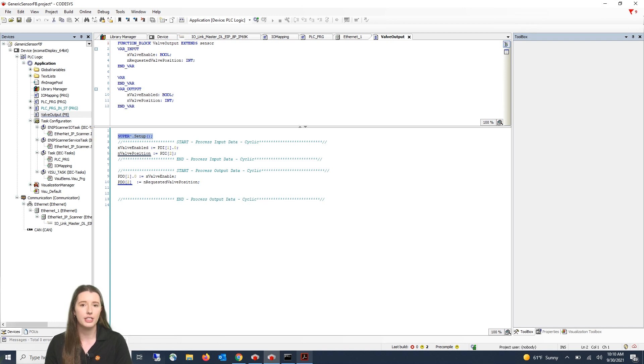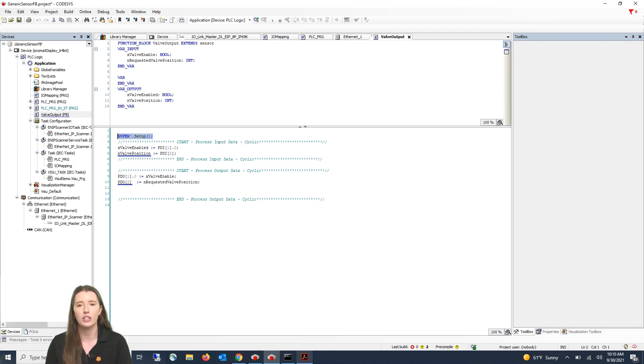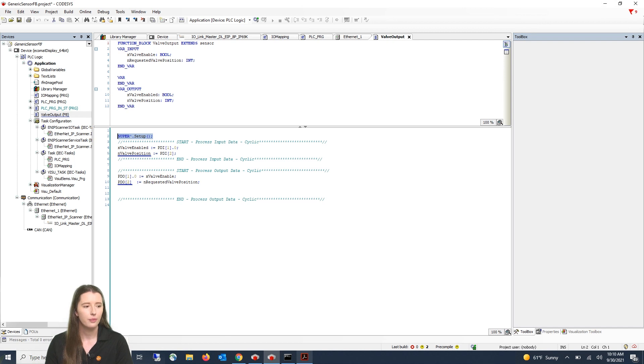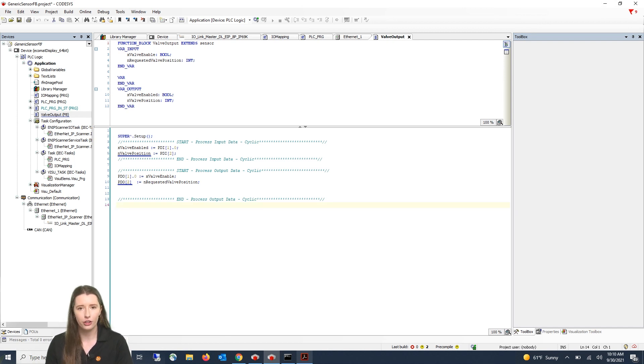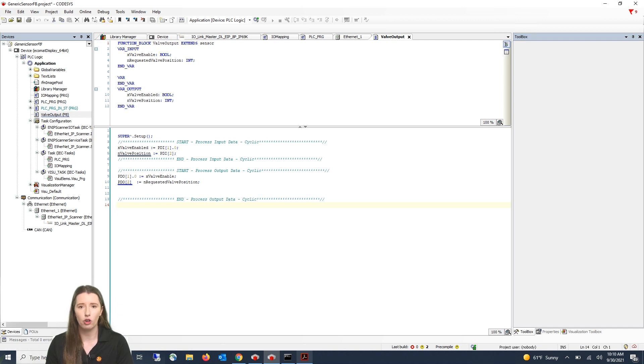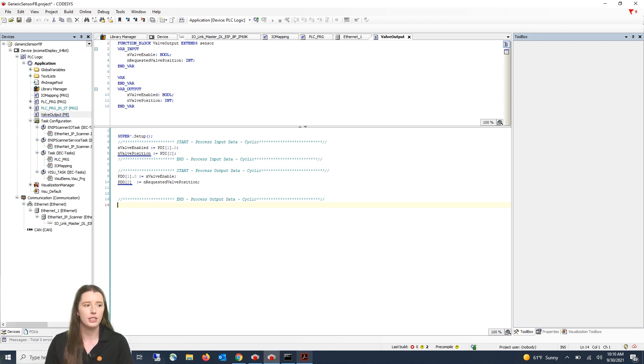This includes the master cyclic data, the port location, diagnostic data such as vendor ID and device ID as well as all of the process data. You would then look at the IODD mapping of your third-party device in order to manipulate that raw data and get it into something that is usable data as you can see here we did it in our structured text below.